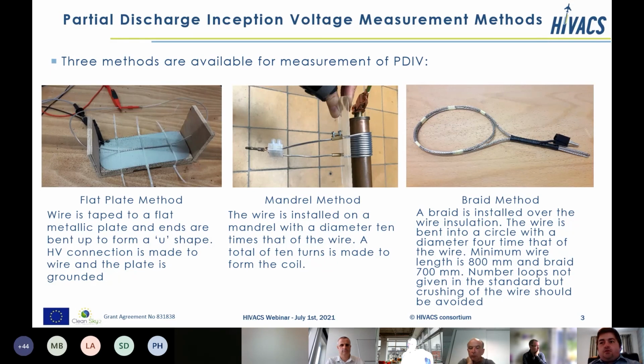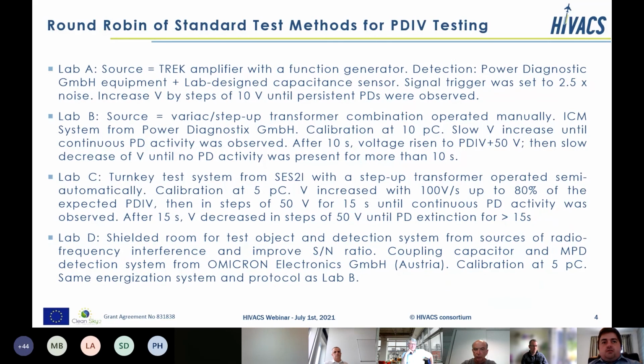And then finally, we've got the braids method, in which you make a loop of wire, where, if I get my terminology correct, the radius is 4 times the diameter of the wire. There's no specification on the number of loops to make, but the standard does say that you should use at least 850 millimeters of wire, of which 750 of those millimeters are covered by braids. So in the round robin, the 4 different labs in the consortium participated in the testing. These are the details of the different test methods.